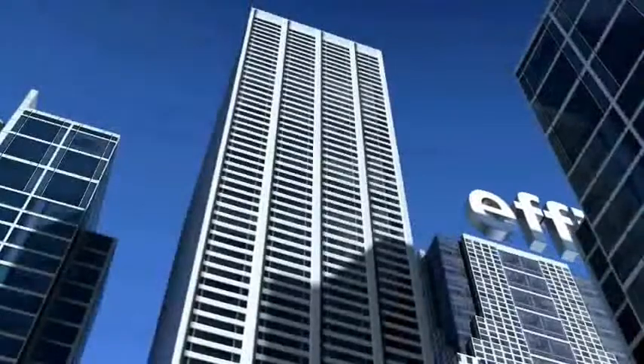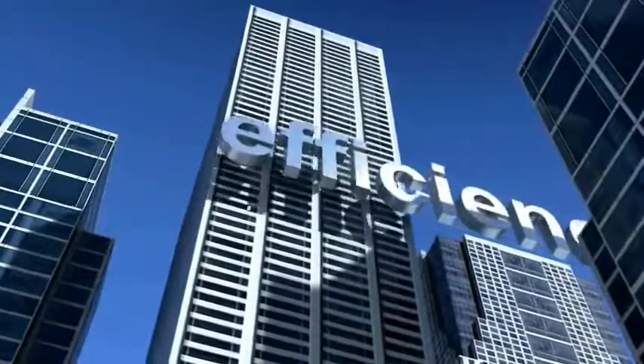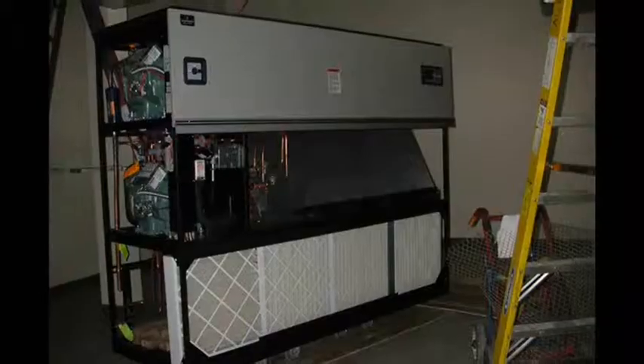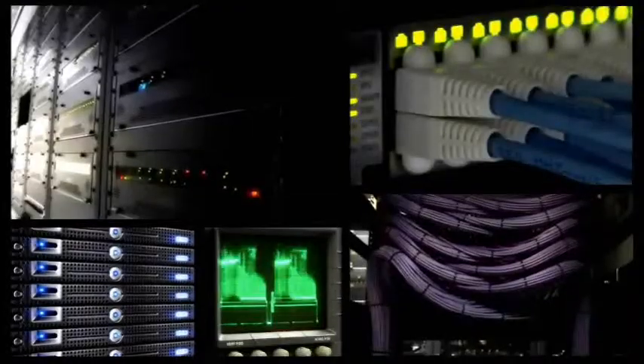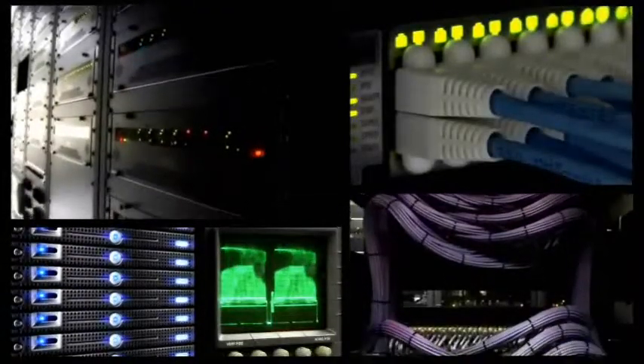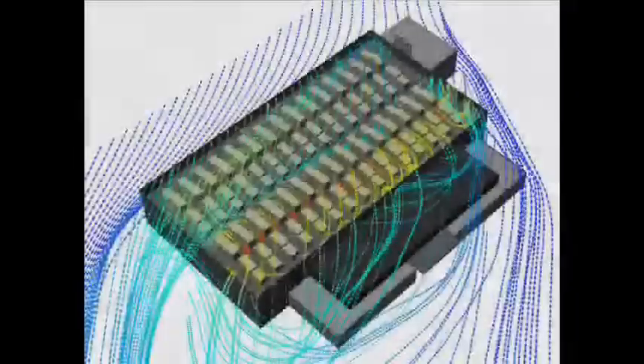Our highly unique service can help you optimize cooling in your facility, our goal being to reduce operating costs, increase cooling capacity, improve CRAC redundancy, and enhance equipment reliability at a mere fraction of the price of using CFD or other tools. Our strategy is simple. We detect airflow and cooling deficiencies using strictly measured and not modeled data.